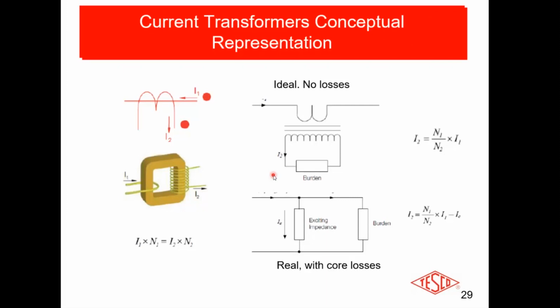Not so with instrument transformers. Why is that? Because of the basic design. Remember I was telling you about the ratios. This is the ratio. Coming in, I have 1 turn. Coming out, I have 10 turns, let's say. That would mean I would have a 50 to 5 transformer. 10 turns to 1 turn is the same as 50 turns to 5 turns. Why do we go to 5? Again, because back in the 1890s, that was the sweet spot for our polyphase meters or for our transformer-rated meters.